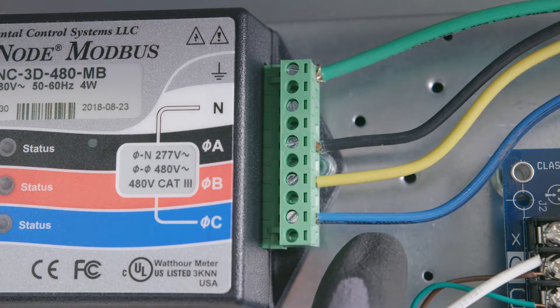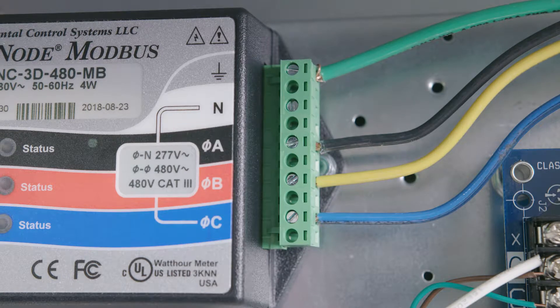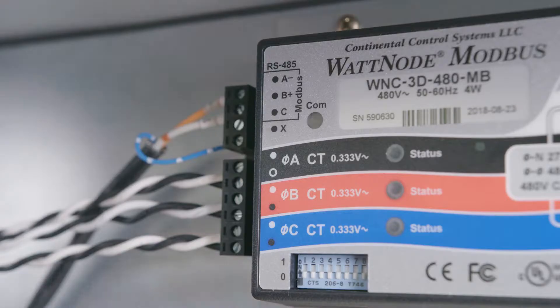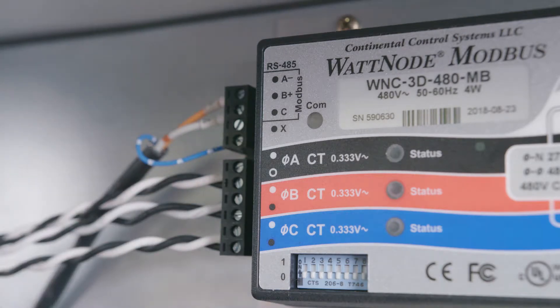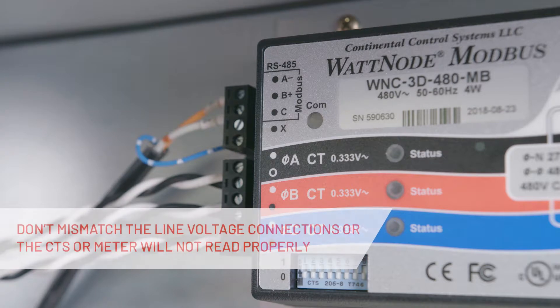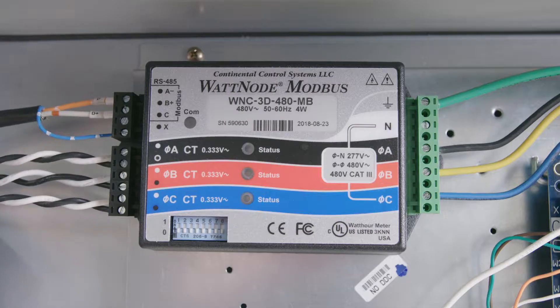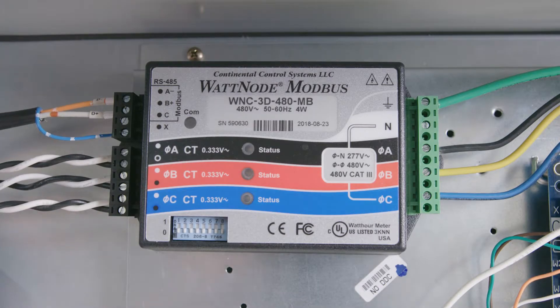On the right-hand side, you have terminals for the A, B, and C phases of power, which need to be connected to the line voltage. On the left-hand side, you have terminals for A, B, and C phases, which need to be connected to the CTs. Please note that the line voltage connected to line A must have the CT connected to that same line voltage. You can't mismatch the line voltage connections and the CTs, or the meter will not read properly. The phases have to be correlated to A phase, B phase, and C phase.